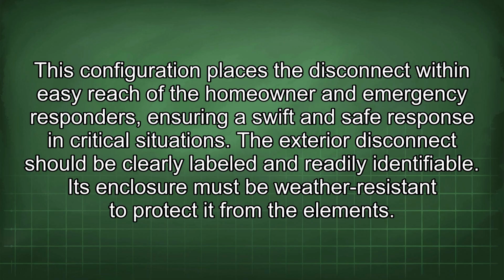This configuration places the disconnect within easy reach of the homeowner and emergency responders, ensuring a swift and safe response in critical situations. The exterior disconnect should be clearly labeled and readily identifiable. Its enclosure must be weather resistant to protect it from the elements.